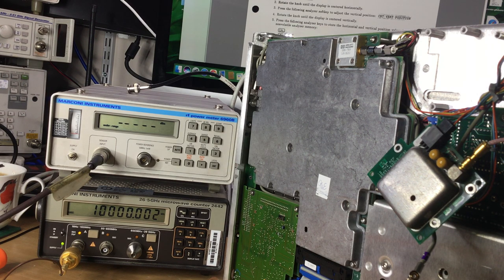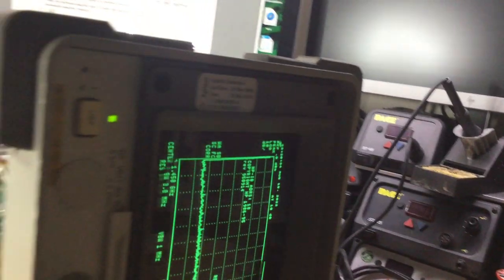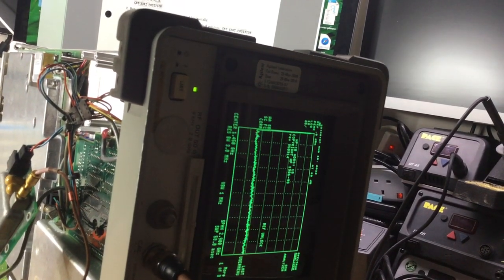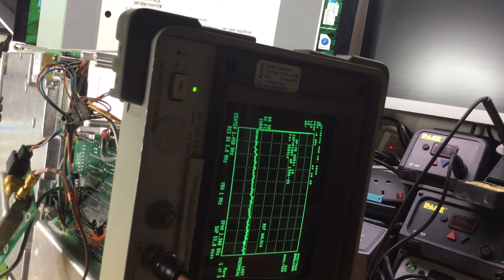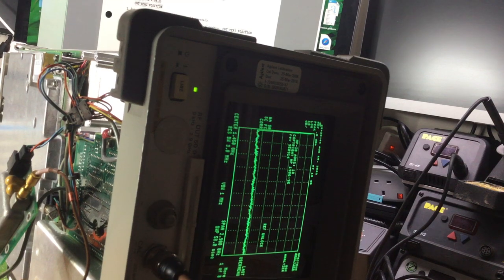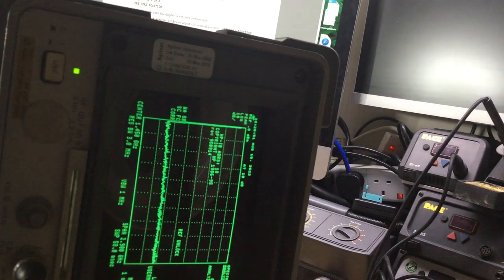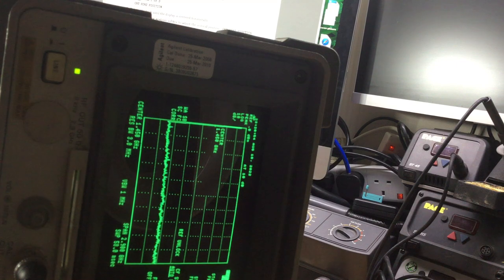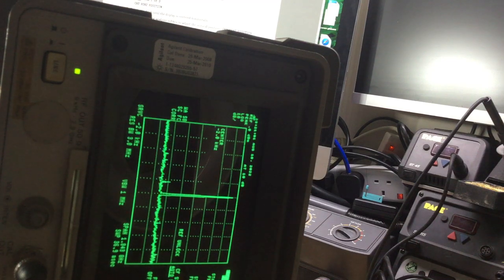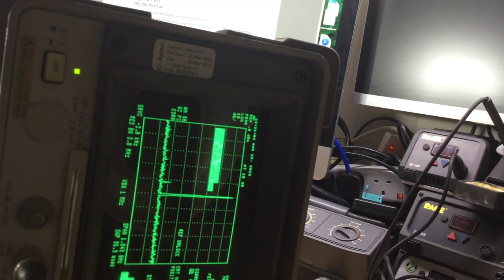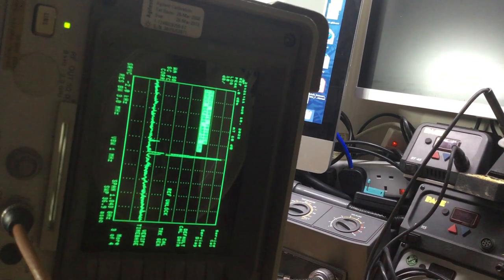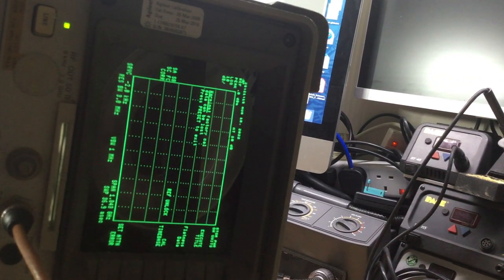Now what I will do, I'm just going to see if I can go into the calibrate menu, which was where we selected calibrate. I just want to check that the fine adjust works, although it may not adjust the 10 meg reference oscillator. It might be, but we'll have a look.